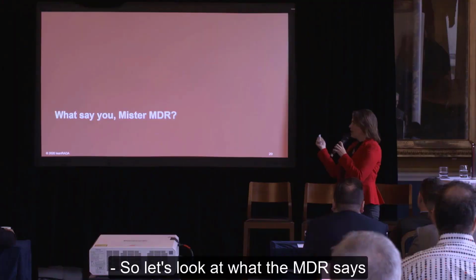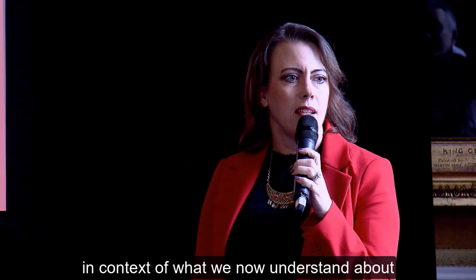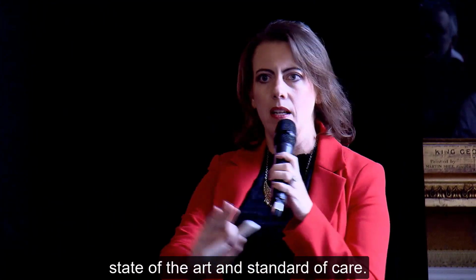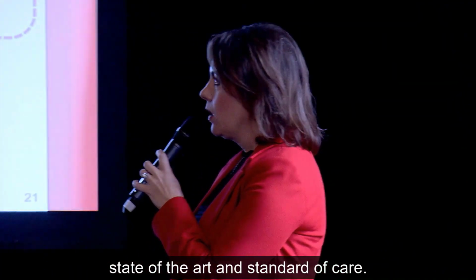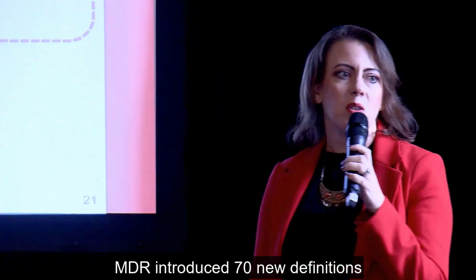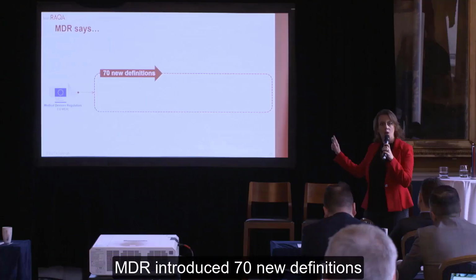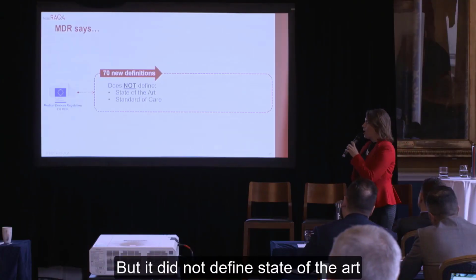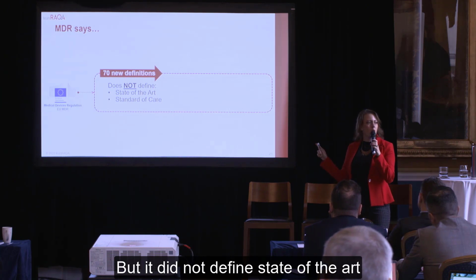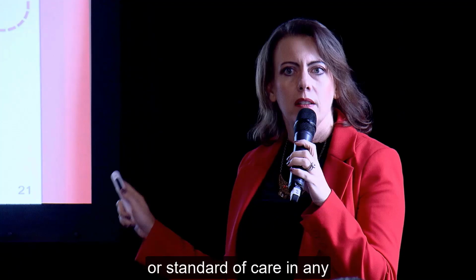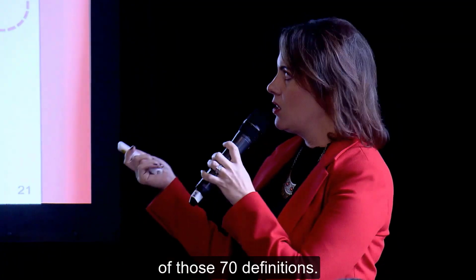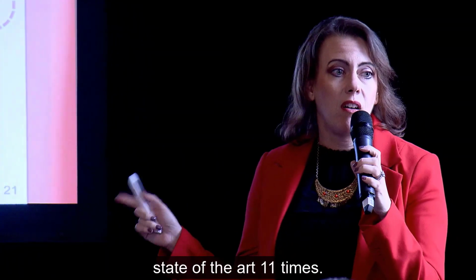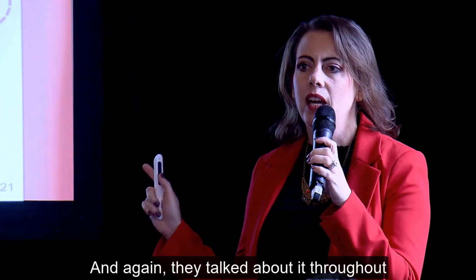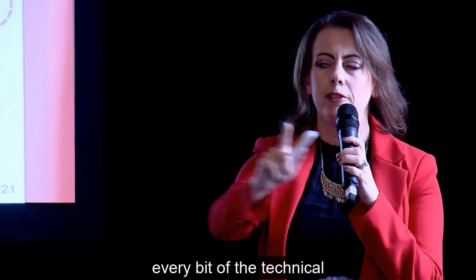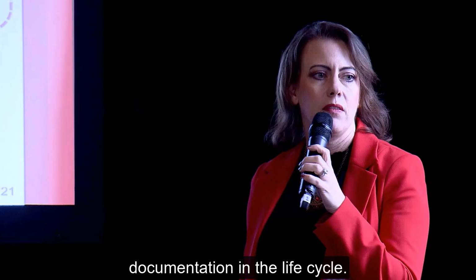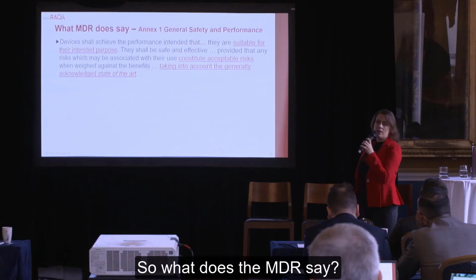So let's look at what the MDR says in context of what we now understand about state of the art and standard of care. The MDR introduced 70 new definitions over the MDD, but it did not define state of the art or standard of care in any of those 70 definitions. But they did talk about state of the art 11 times, and again, they talked about it throughout every bit of the technical documentation in the life cycle. So what does the MDR say?